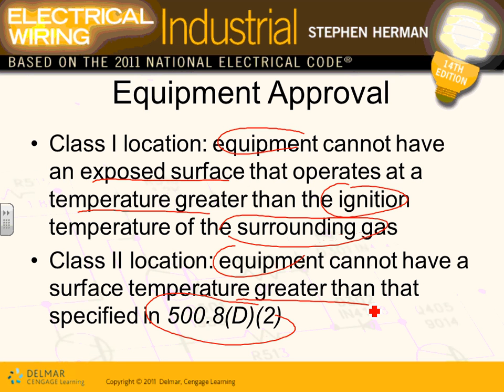Then in a Class II location, guys, they use dust ignition proof. They call it dust ignition proof. Dust ignition proof doesn't allow the dust to get into it. It's sealed, bolted together, and the temperature of the equipment cannot reach an igniting temperature that can ignite the dust. Any comments, guys, about the equipment? Why is it so important for the equipment approval?